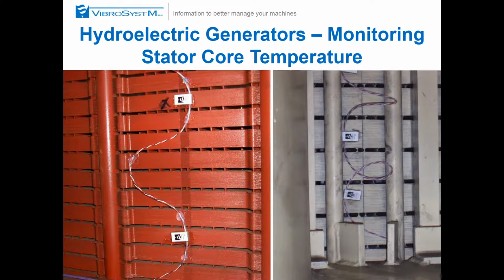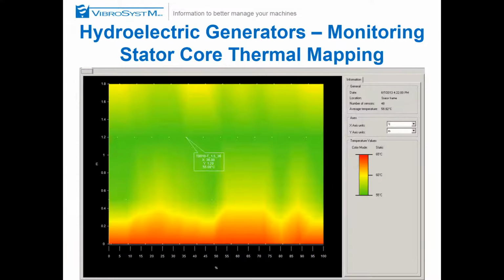And you can monitor stator core temperature as well, same type of sensor, different location, and you can get an interpolation of the entire stator core, give you an indication if you have hot spots. This is real data here where you can see that the bottom part of the stator was much warmer than the upper part.